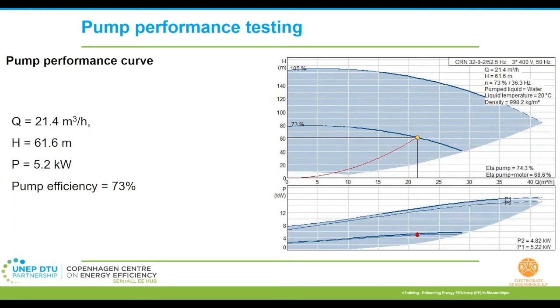So let's say I can measure the head with respect to my on-site pressure gauges, both on the suction and the discharge side. I will measure the head. Then if I draw a line like this, I can find out what is the efficiency of the pump that is operating. Here now it is 73%. Then if I further extend the line, I'll know what flow my pump is operating at. And then this also gives me the power consumption. So it is mix and match. If you have any of the parameters, you can find the other parameters using the pump curves. So yes, if you do not have the resources for measuring and doing all these activities, the simplest form is to at least demand this pump curve.